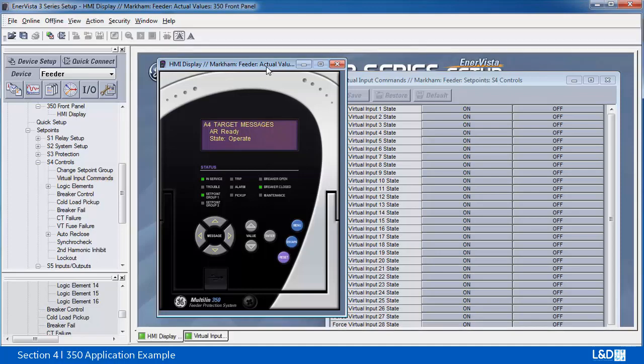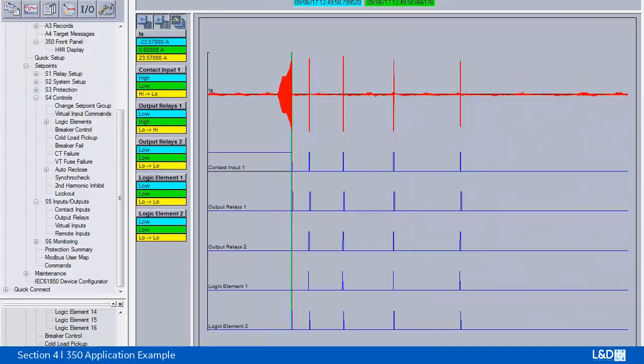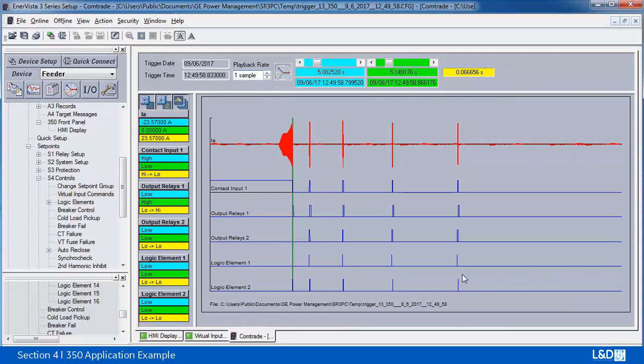We're going to use RTT to inject the current and see the auto reclose 4 shot process. Okay, so that's the 4 shots of the auto reclose. Then we can launch the oscillography. Okay, so now the waveform is downloaded. We can see that the AC current applied caused the breaker to open, tripped the relay on relay 1.